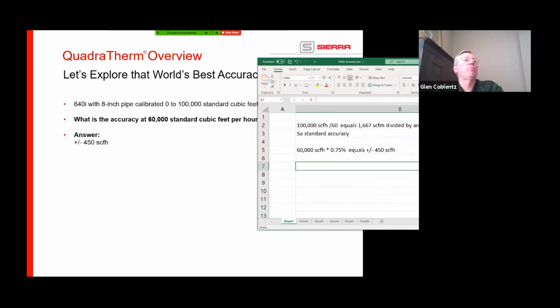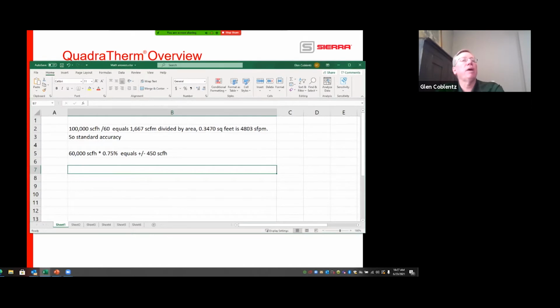Now, those of you that are still wondering, well, how in the world did we come up with that? Here is the math. 100,000 standard cubic feet per hour divided by 60 gives you SCFM, divided by the area of the pipe gives you your standard feet per minute. So the standard accuracy is that. So it's 450 standard cubic feet per hour because it's above the 50% of the calibrated full scale.